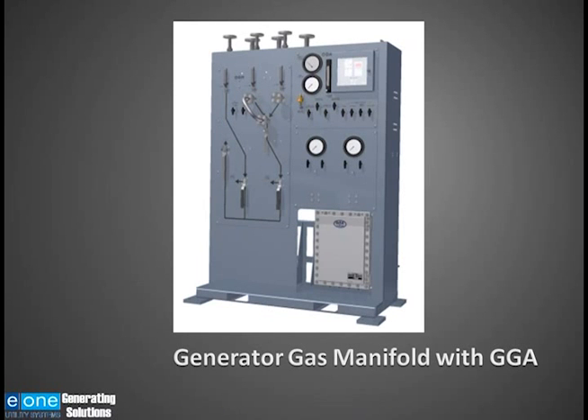And then you can see the spool piece, that little U piece that's in the piping. And that's a removable part that allows you to put either hydrogen in the machine or air in the machine, but it will not allow you to put both in at the same time. Again, this is not foolproof. It is still possible to put hydrogen and air in that generator by switching that. So it's very important that you know what gas is in that generator.